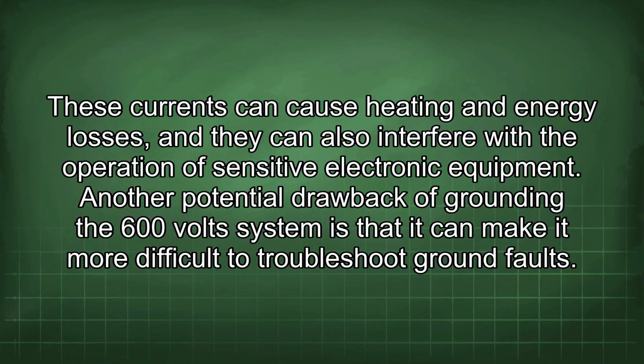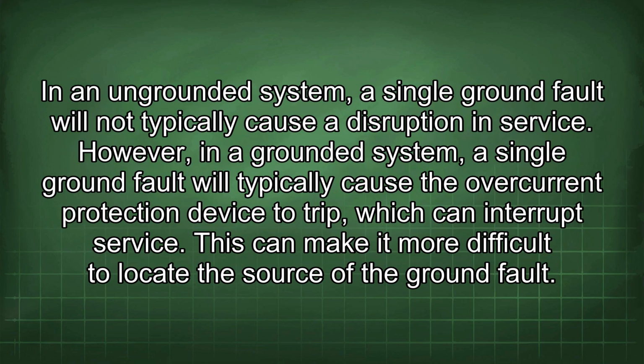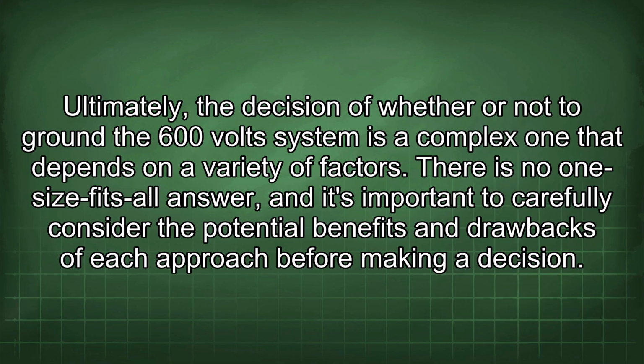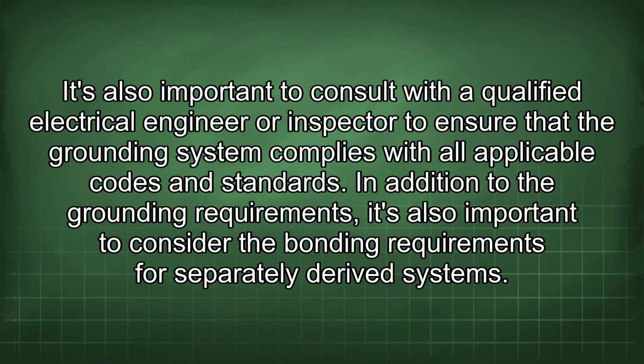Another potential drawback of grounding the 600-volt system is that it can make it more difficult to troubleshoot ground faults. In an ungrounded system, a single ground fault will not typically cause a disruption in service. However, in a grounded system, a single ground fault will typically cause the overcurrent protection device to trip, which can interrupt service. This can make it more difficult to locate the source of the ground fault. Ultimately, the decision of whether or not to ground the 600-volt system is a complex one that depends on a variety of factors. There is no one-size-fits-all answer, and it's important to carefully consider the potential benefits and drawbacks of each approach before making a decision. It's also important to consult with a qualified electrical engineer or inspector to ensure that the grounding system complies with all applicable codes and standards.